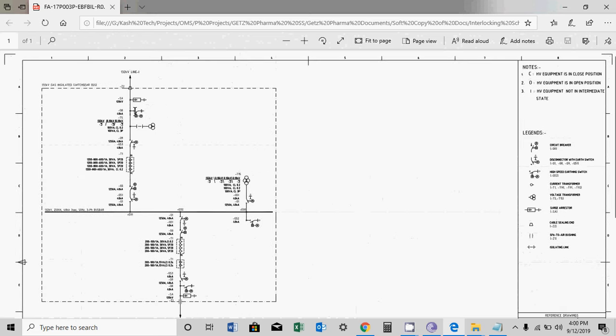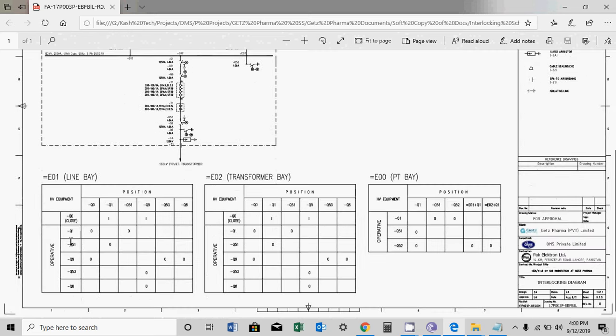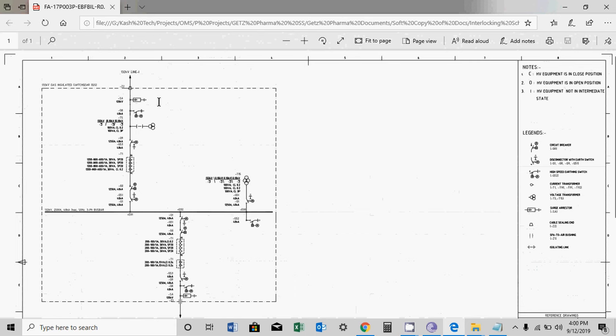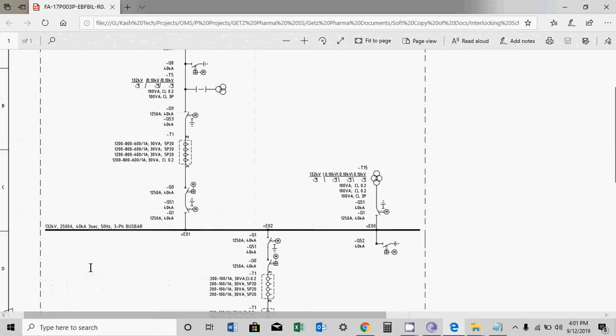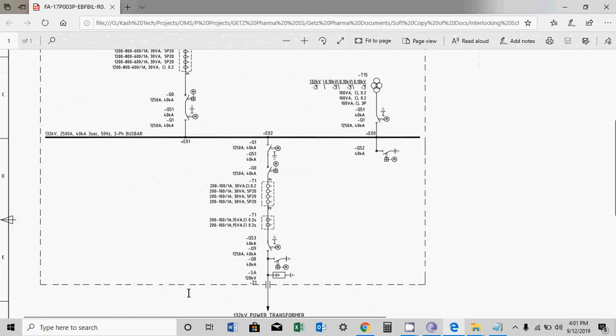So isolators should be closed completely or open before you can operate the breaker. Second is the earth switch Q51. You can operate the earth switch if Q1 is open. We can see here, Q1 is here. So you can close the earth switch if the isolator is open, and this is mechanical interlocking. So this is two-in-one, built-in earth switch and isolator. You cannot close it if this isolator is open. This is mostly mechanical interlock.